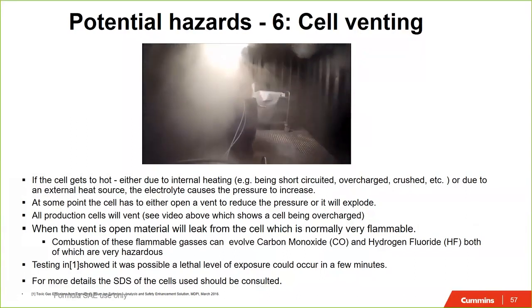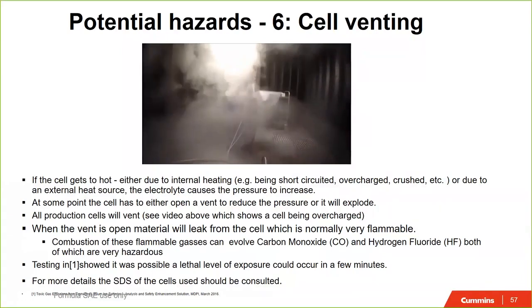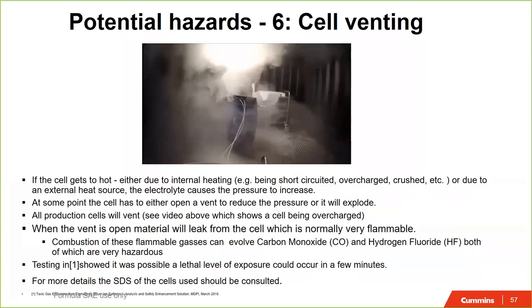The gases that you see in here are a mixture of carbon monoxide, carbon dioxide, and hydrogen fluoride. The carbon monoxide and the hydrogen fluoride are the 2 you want to worry about. One's a silent killer. The other one creates hydrofluoric acid inside your lungs and will burn you from the inside out. However, it takes, generally speaking, several minutes, even in a chamber this size, to reach the hazardous levels. As soon as you see a cell fail, smoke coming from a pack, get away from the pack. If you're in a building, evacuate the building.